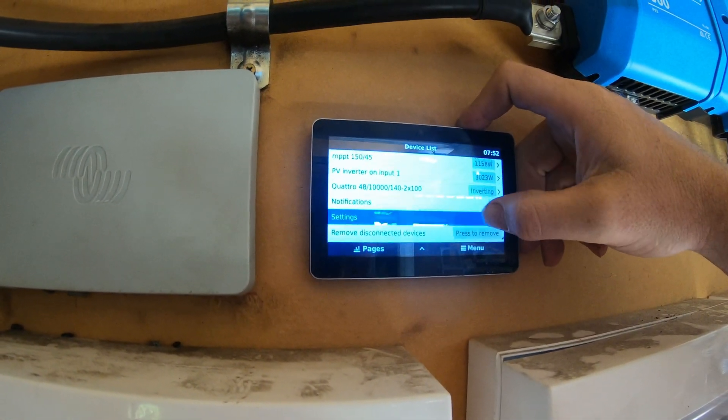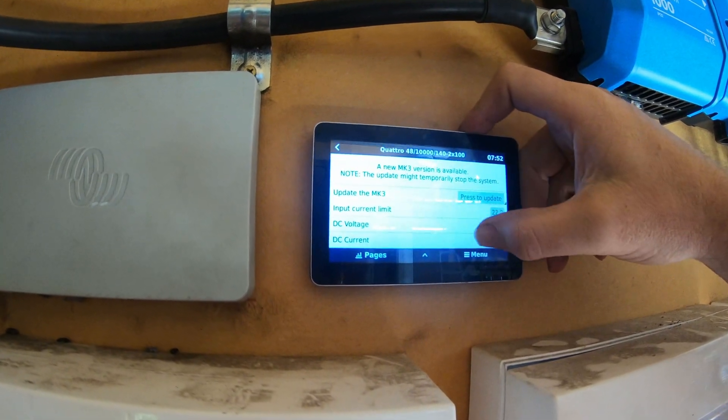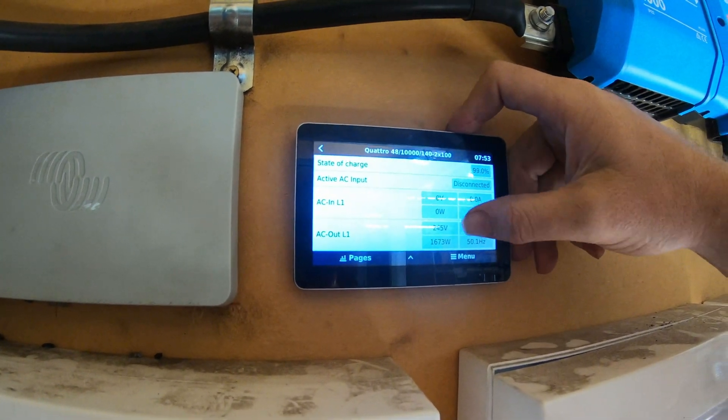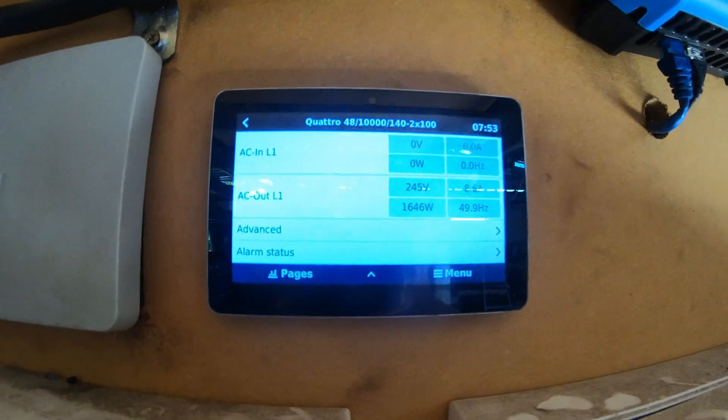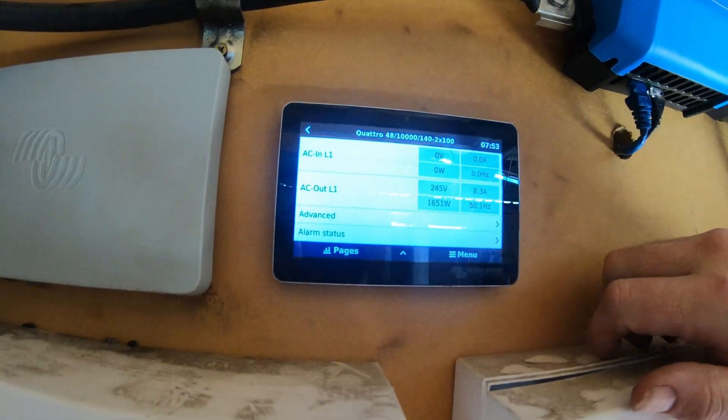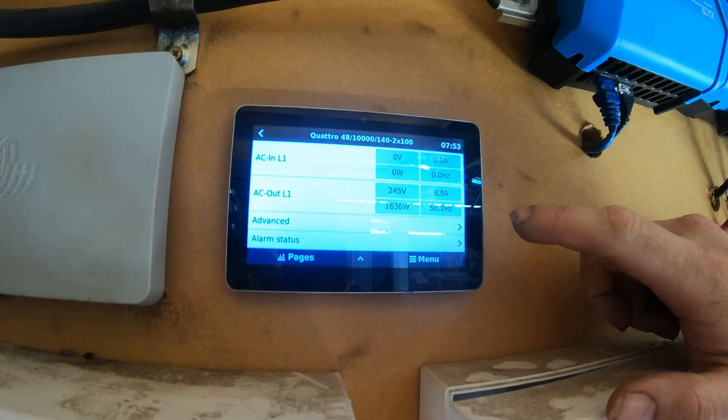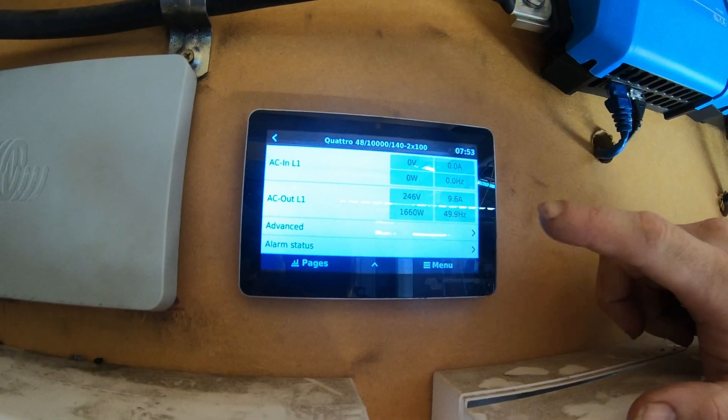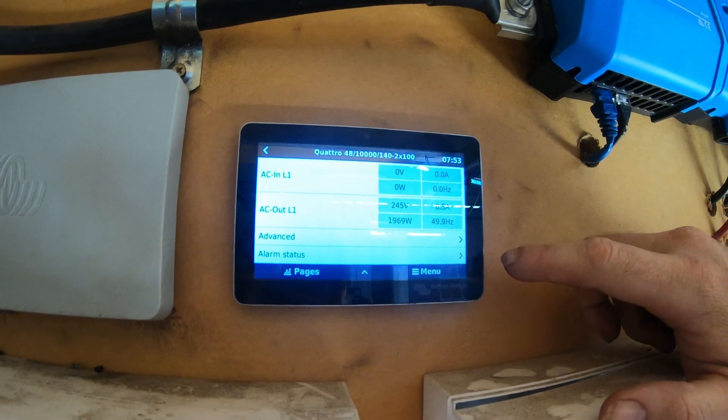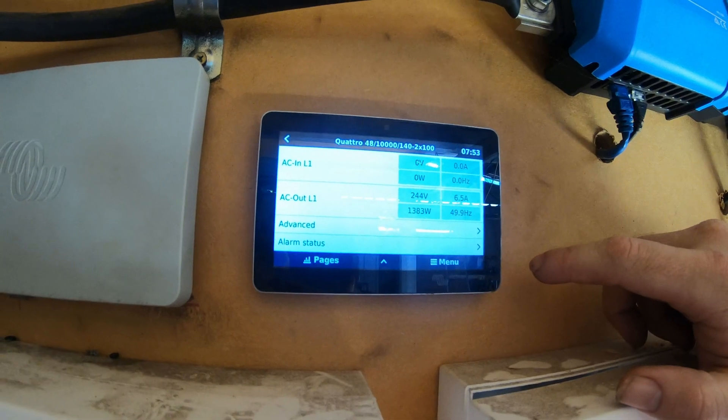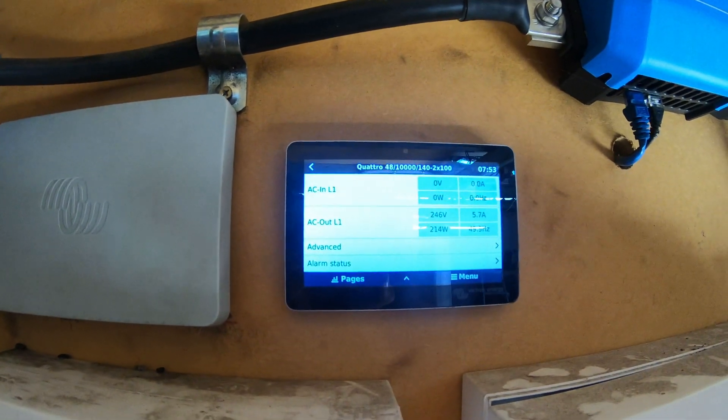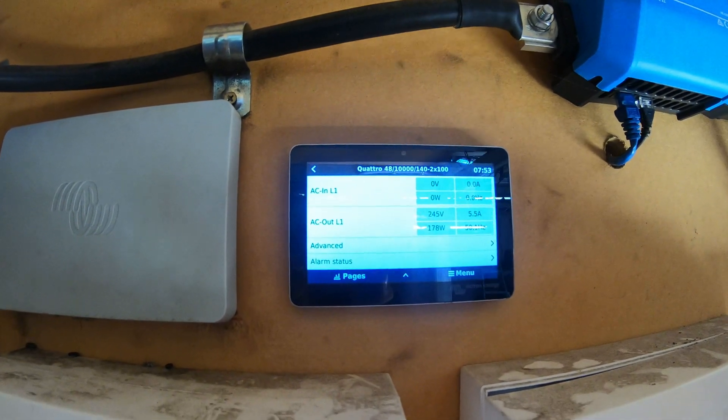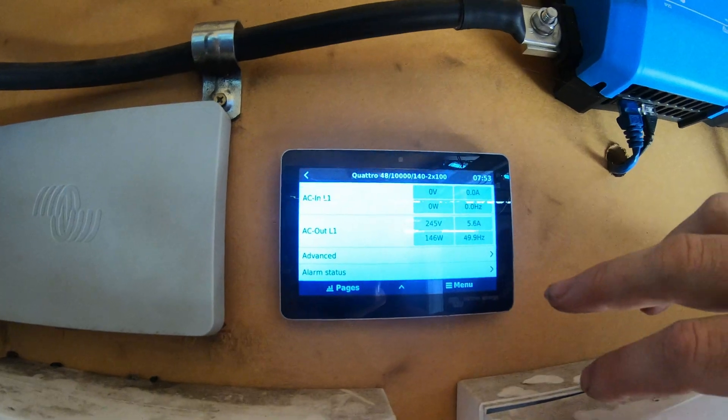Like when we hear that noise coming out of the - I've got to do an upgrade, I'm not doing that right now - 245 on AC out. That's interesting, I wonder what's causing that noise. When it happens on the Quattro 2 in the caravan, it's usually because the inverters default at 230 volts, and if you put the self-consumption or ESS on it, it's got to get in sync with the grid. If your inverter's at 230 and it's trying to get in sync with the 240 volt grid, you'll hear that noise a little bit. But I'm not attached to anything else, so I assume it's got something to do with the AC-coupled solar over there.